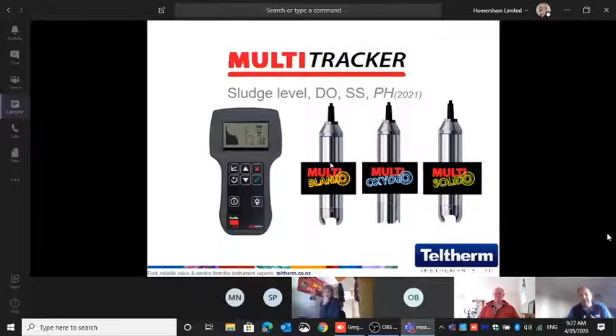We normally use that, if you're interested, to determine the best position to mount the unit. Also for solids, that's what I basically use. If you want to measure solids somewhere, we just poke it in with this unit and we can tell straight away whether we can measure it, yes or no. It's just a portable. There are quite a few smaller councils that bought the portable unit because they don't want to spend $18,000 on a sludge blanket or $10,000 on the inline unit or the submersible unit. They go with the multi-tracker, the portable unit.